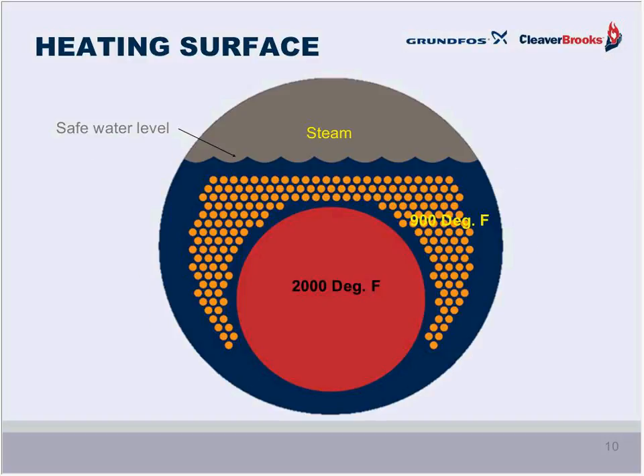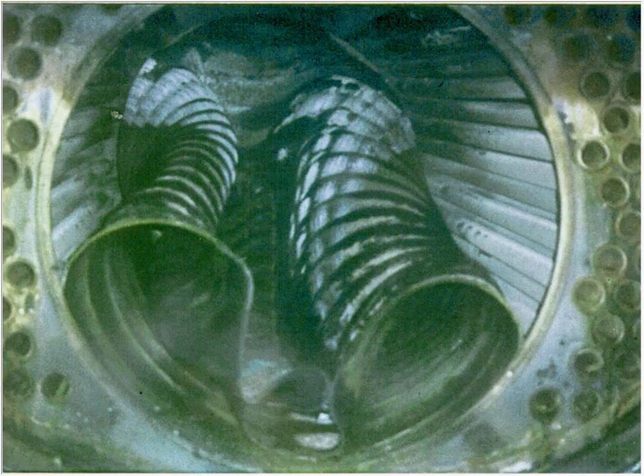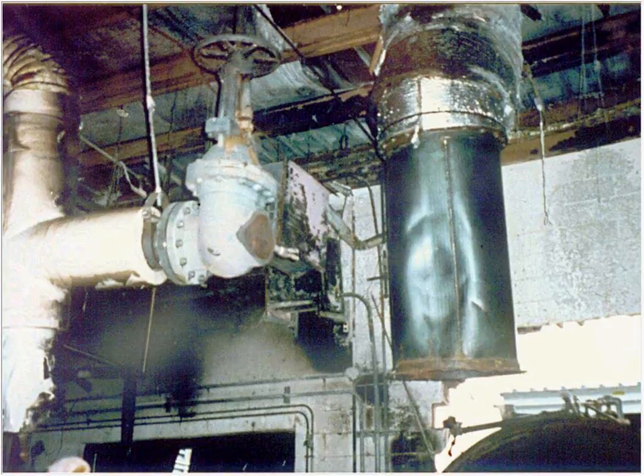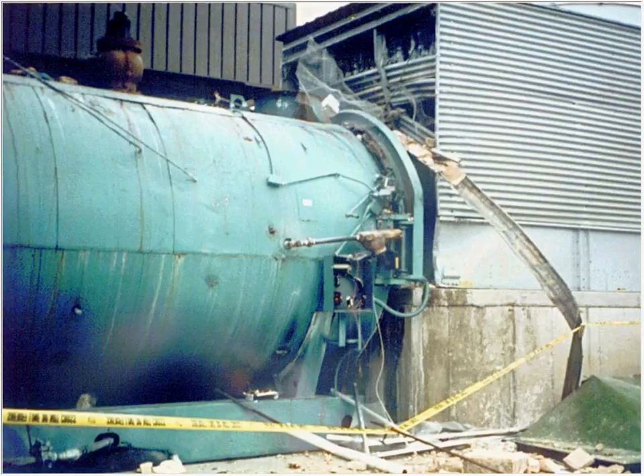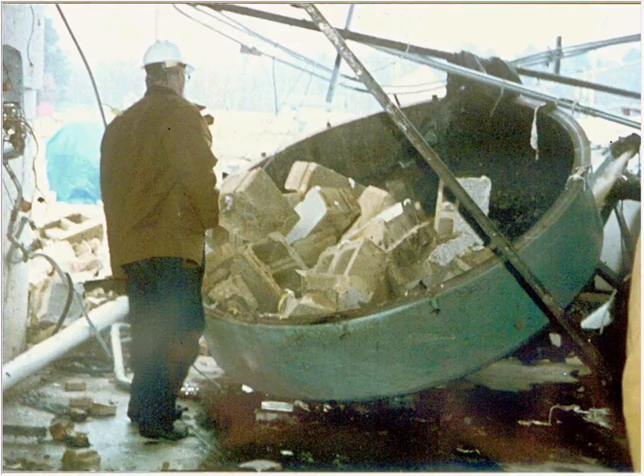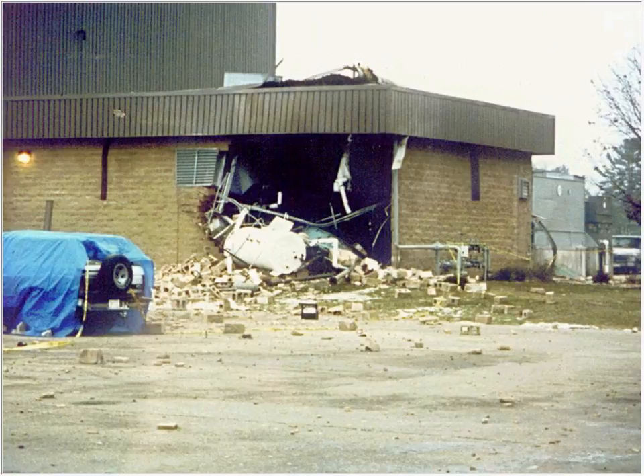So the water level in the boiler is a critical dimension as it not only provides the substance for the steam to be created, but also provides the assurance the boiler doesn't experience an overheating condition where the boiler tubes and furnace are compromised, causing a rupture when a significant amount of the water in the boiler suddenly expands 1,600 times with tremendous force, ripping the boiler from its moorings and tearing it from its piping connections, sending, in this case, a 65,000-pound monster out of the building, and at the same time, this 10,000-pound rear door is torn loose, exiting the rear wall of the boiler room, but while it's on its way, also taking out the deaerator.